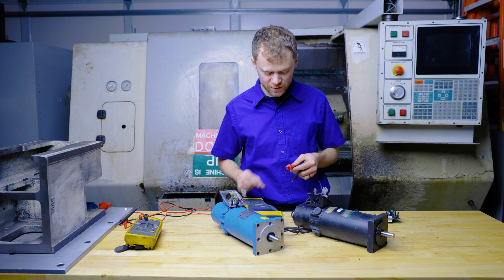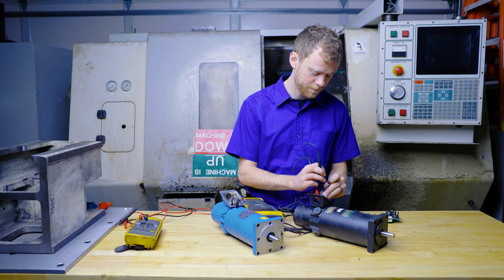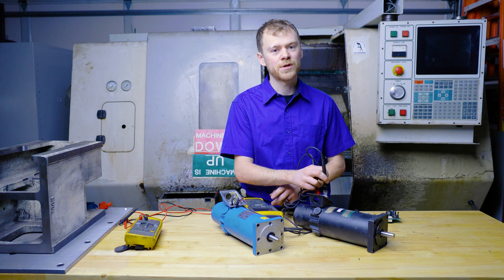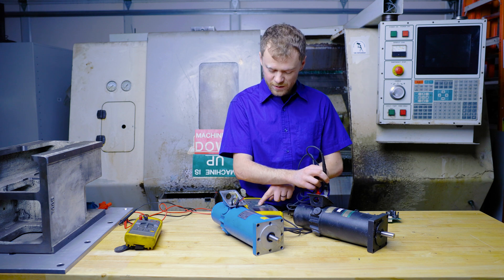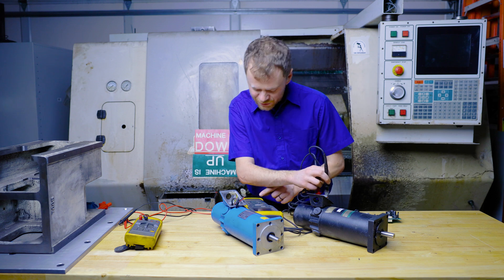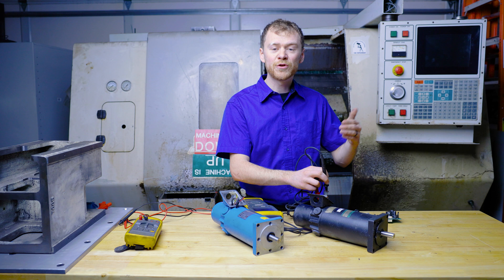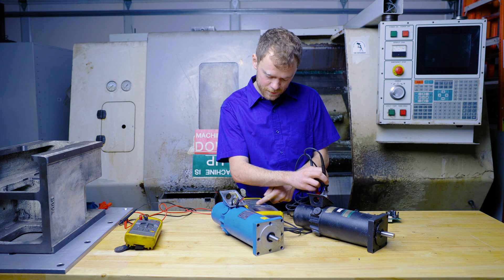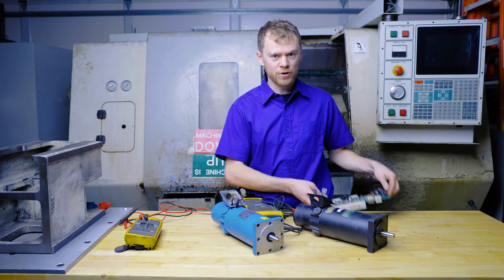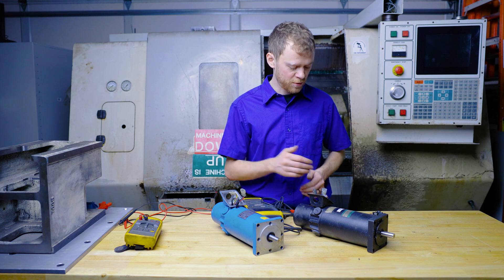Now let's check the bad motor, starting at 250 volts. It doesn't even build voltage — the hipot meter says it can't build voltage, direct short. It's like 70k to ground. At 500 volts, still 70k to ground, and it only built up to 100 volts instead of 500. At 1000 volts, still 70k to ground — this motor is shorted. Anything less than 1 meg ohm to ground and you run the potential of blowing up your amplifier, because the transistors cannot handle that much current through ground.